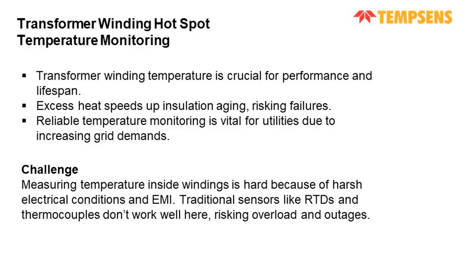So traditional sensors like RTDs and thermocouples often tend to fail here because of EMI and lack of electrical isolation. Moreover, calculated temperature values based on external measurements or models are not reliable enough for critical decisions. Without precise real-time data, utilities risk transformer overload, accelerated insulation aging, and unexpected outages.